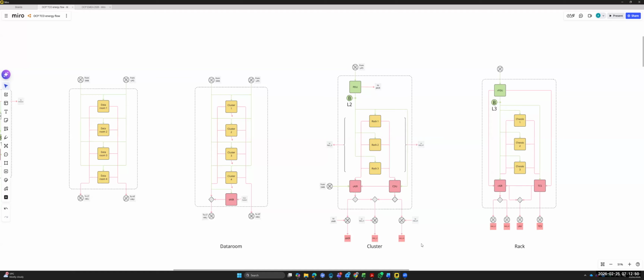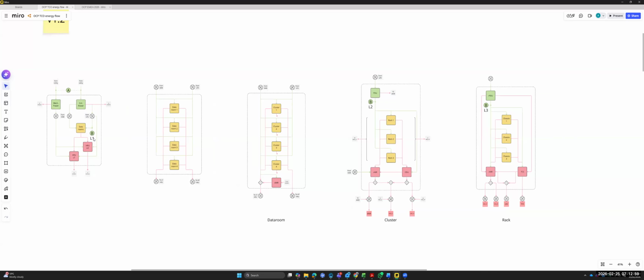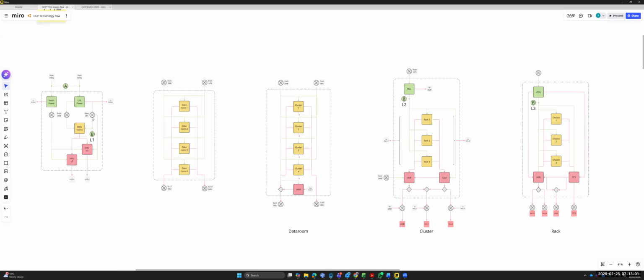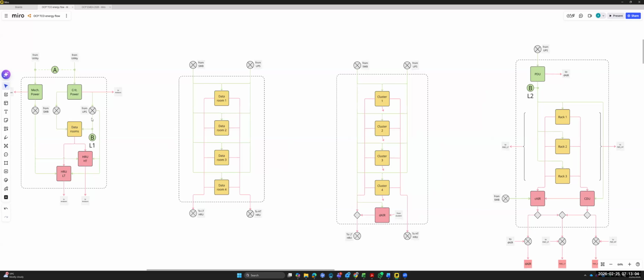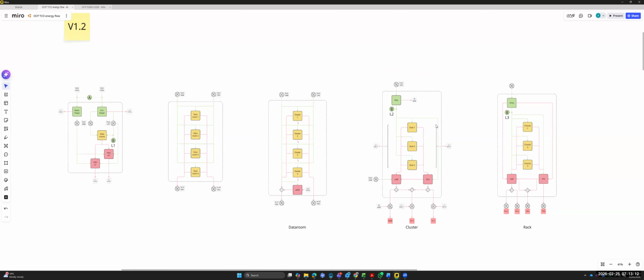And where is L1 now? Is it still data room, or is it full facility? L1 is full facility - basically the critical power out of the UPS that enters the data room. So those locations are still aligned as they are defined by the Uptime Institute for the PUE calculation.